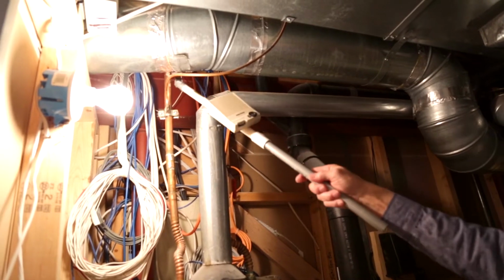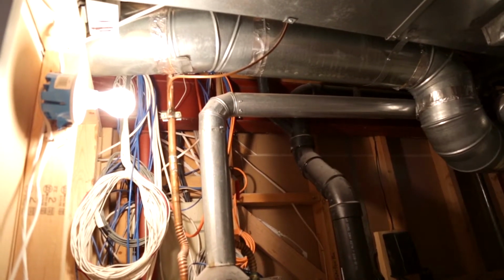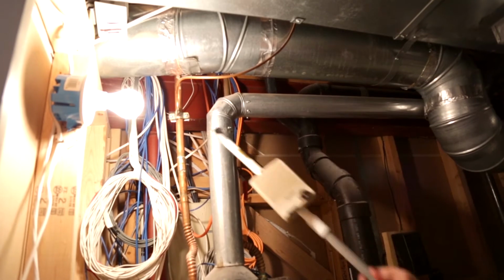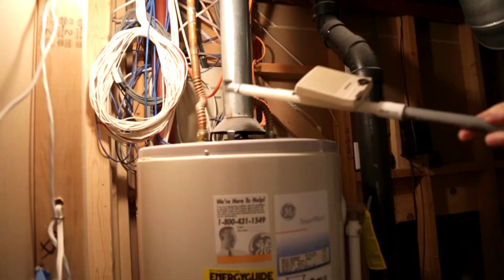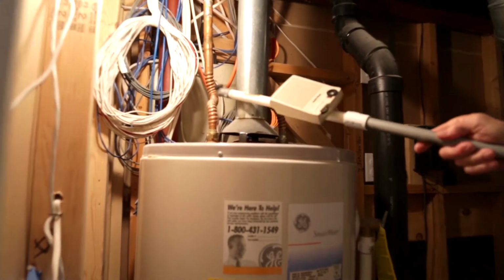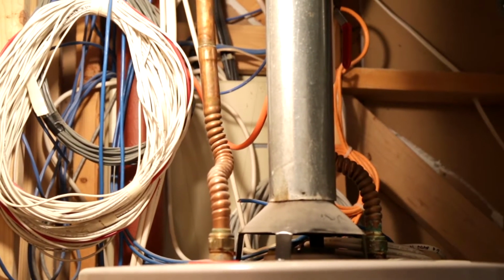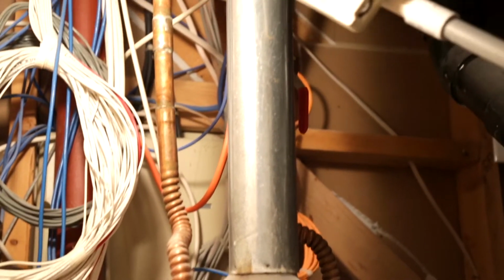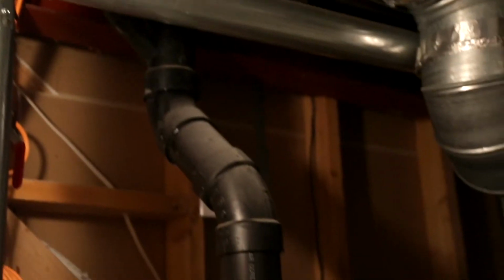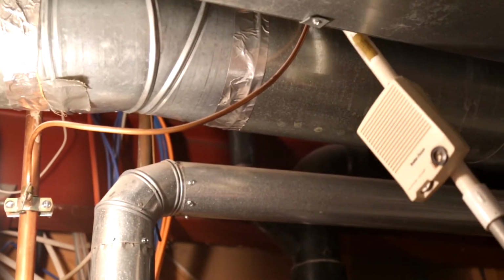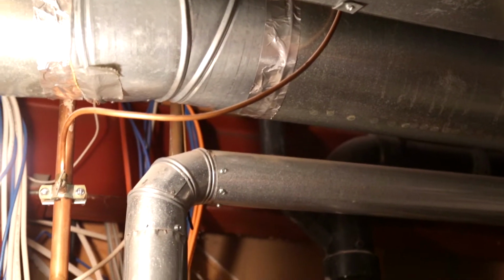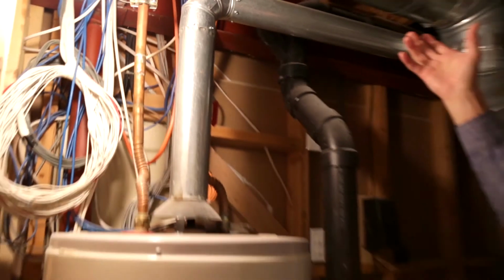So this is the pipe we've been tracing, coming in up off the ceiling and heading for the hot water heater. You'll notice that there is apparently no current flow below this place where the line for the refrigerator ice maker takes off. And if we test that out, we see that that's going right upstairs to the refrigerator.